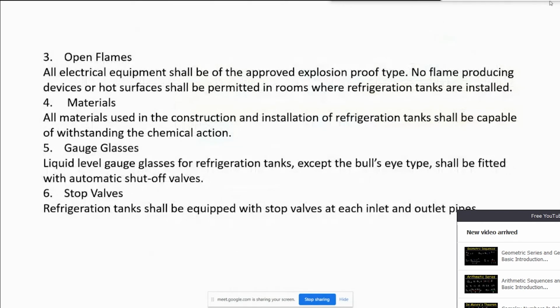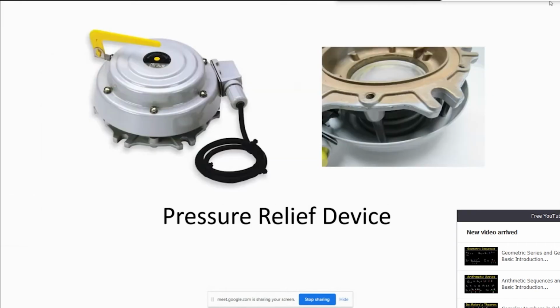Open flames. All electrical equipment shall be of the approved explosion-proof type. No flame-producing devices or hot surfaces shall be permitted in rooms where refrigeration tanks are installed. Materials. All materials used in the construction and installation of refrigeration tanks shall be capable of withstanding the chemical action. Gauge glasses. Liquid level gauge glasses for refrigeration tanks, except the bullseye type, shall be fitted with automatic shut-off valves. Stop valves. Refrigeration tanks shall be equipped with a stop valve at each inlet and outlet pipe. Pressure relief devices.